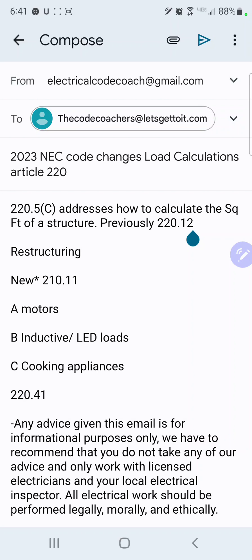Just to clarify: if we're doing a load calculation and we're trying to figure out the square feet of the home to determine our general square foot load calculation for lighting and general receptacles, historically we would use the outside dimensions of the house. So if it was a 30 by 30, we would use those dimensions, but we would not include garages, open porches, and basements or areas that are not adaptable for future use — which is subject to your and your inspector's interpretation.